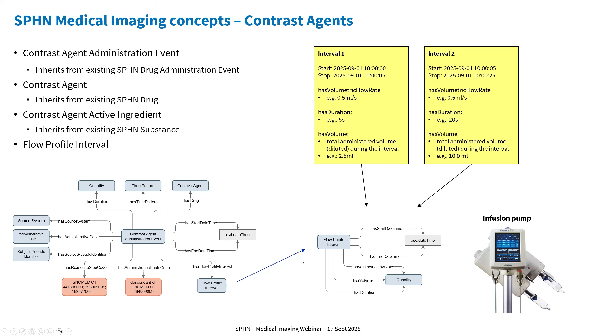As said, the contrast agent is usually provided with an infusion pump. And you can specify the flow profile of this infusion pump. For example, you have a start time and a stop time. And during this interval, the flow rate was, for example, 0.5 milliliter per second for a duration of 5 seconds. And then the total volume can be 2.5 milliliters. This can all be specified here. There can be a second interval connected as well with slightly different properties, for example.